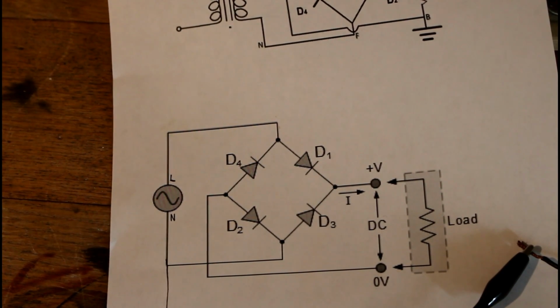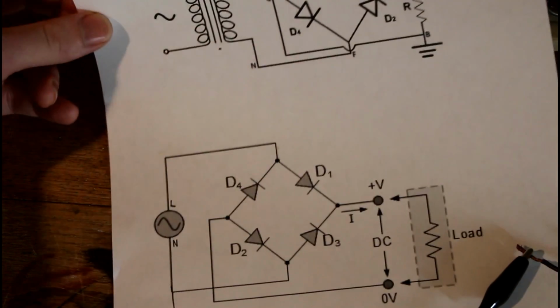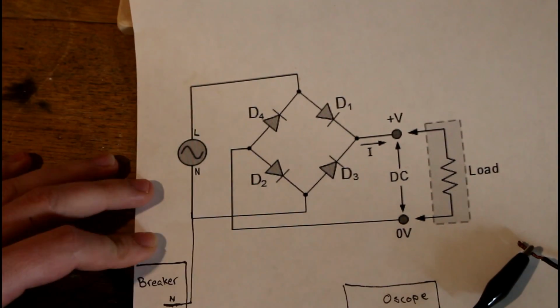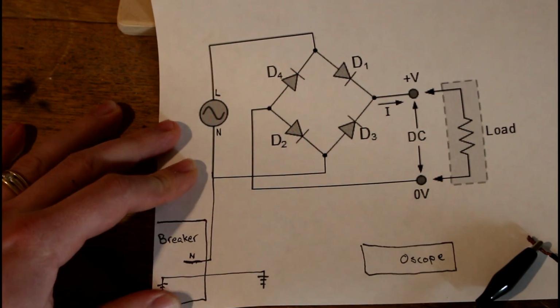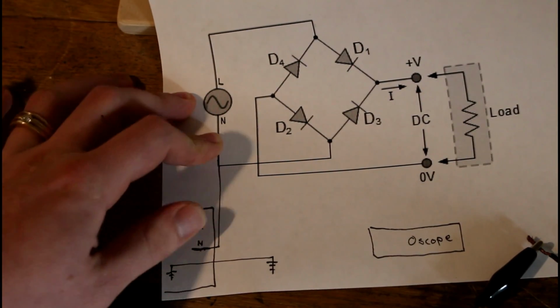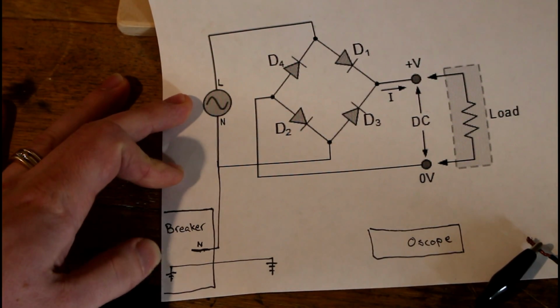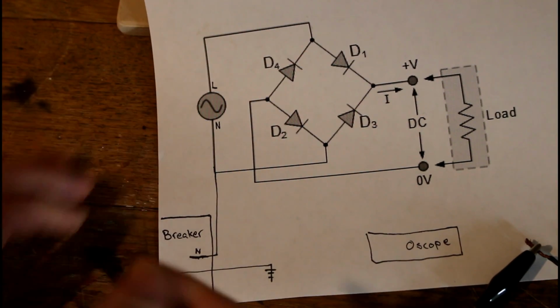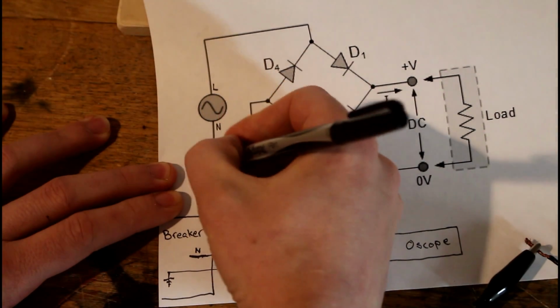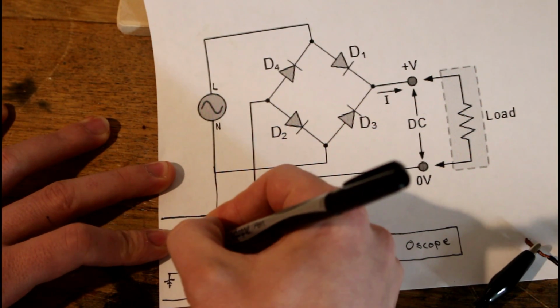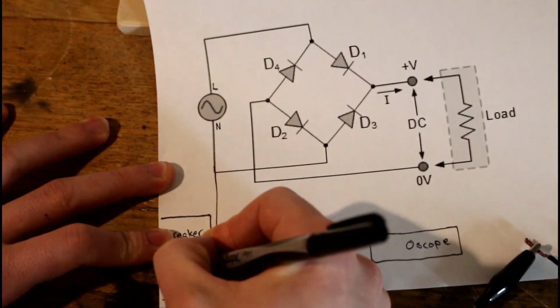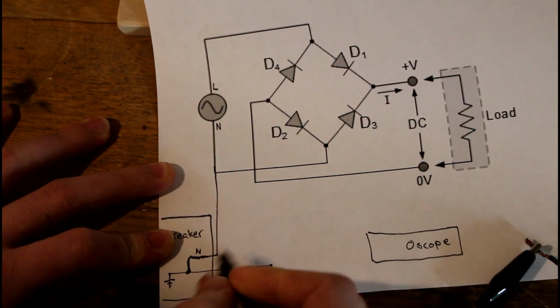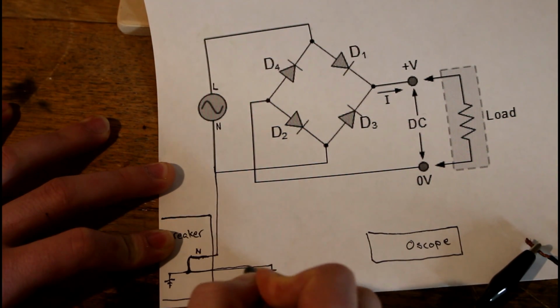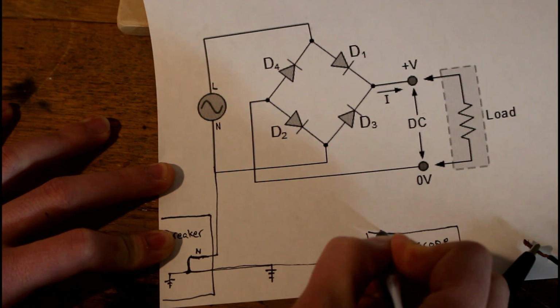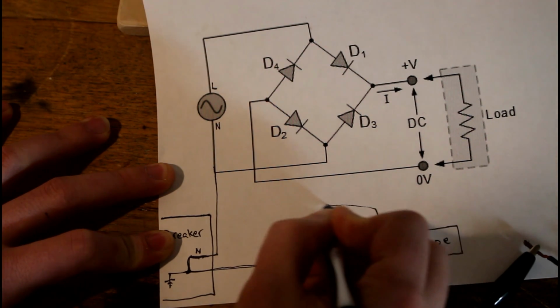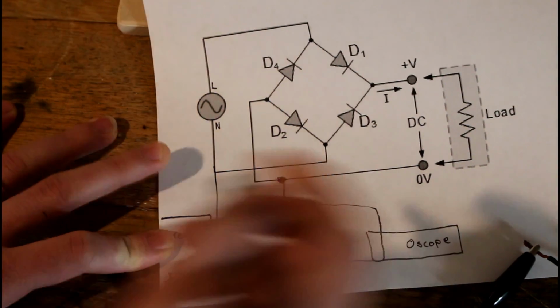The reason for that is, at least in the US, and I'm sure this is true in other countries as well, neutral and ground are connected inside the breaker box. So if you look right here, the neutral line comes down, goes into your breaker box, and is connected over to ground. Now that ground is going to go up into your oscilloscope, and then you connect that ground clip over here. So now look at what you've done.